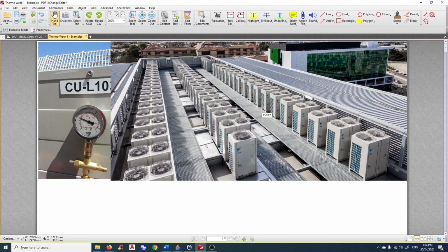We upgraded one of the medical centers, consisting of many VRV condensers. Because this condenser serves multiple floors below, sometimes 5 floors below, we want to be absolutely sure when the subcontractor did the brazing on the copper pipe, there are no leaks. And if there is a leak, you have to find it before all the ceiling and the riser is closed.